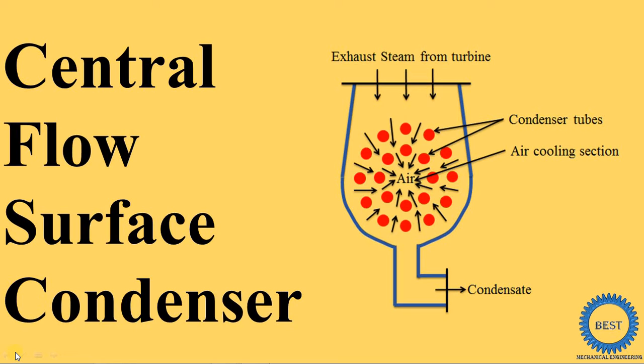You already know what a surface condenser is. In a surface condenser, the steam and the cooling water do not directly come into contact. It means the exhaust steam from the turbine is passed outside the tubes, and inside the tubes, the cooling water is passed. Steam and cooling water are not directly mixed — the tubes act as the medium.